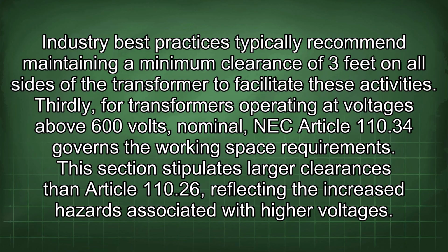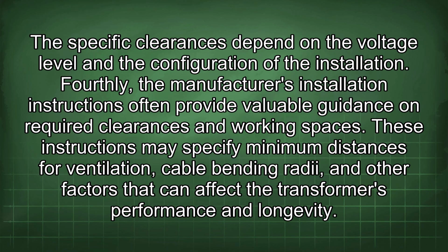Thirdly, for transformers operating at voltages above 600 volts, nominal, NEC Article 110.34 governs the working space requirements. This section stipulates larger clearances than Article 110.26, reflecting the increased hazards associated with higher voltages. The specific clearances depend on the voltage level and the configuration of the installation. Fourthly, the manufacturer's installation instructions often provide valuable guidance on required clearances and working spaces.